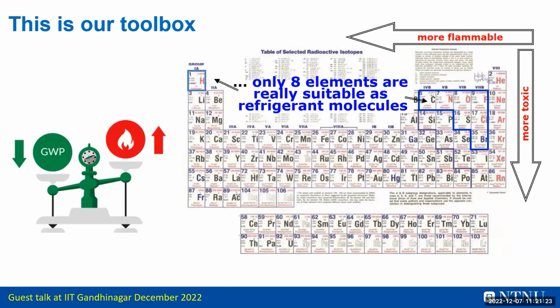The more we go to the left, the more flammable—that's why this is very flammable. So it's always kind of a balance: low GWP means high flammability. So all these new fluids are flammable. That's okay, we can treat that, it's not a problem—the design has to be in accordance.